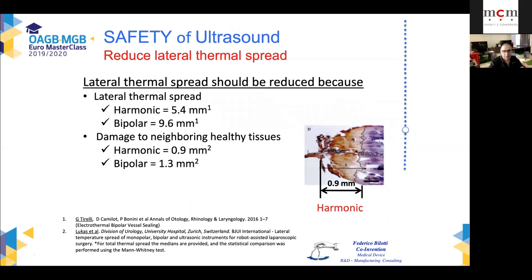Remember the footprint I told you about? 0.9, as Tirelli describes, is the damage to the side of the instrument. 1.3 is the damage to the side of the instrument of a bipolar instrument. So if you have a nerve at 1 millimeter to the ultrasound device, you will not damage it with harmonic energy, ultrasound energy, but you will damage it with bipolar electrical devices.